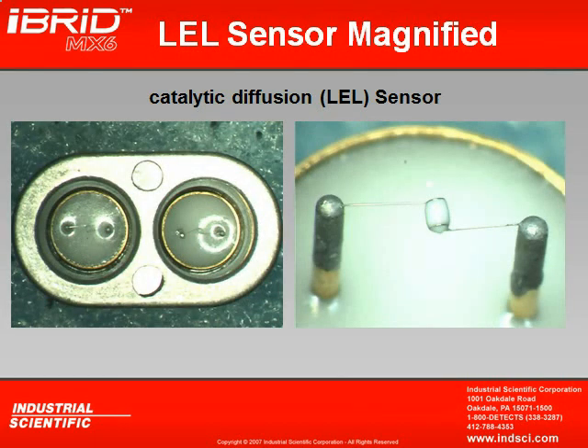So if we could actually see inside of a combustible sensor, this is what we'd see. Now we took these pictures underneath microscopes because, well, that's 1/1000th of an inch thin platinum wire. That's 7 times thinner than a human hair. Pictured on the left, you'll see I have circled, that's actually the sensing bead. Now the sensing bead is very porous, kind of like a piece of charcoal, and that is so that the combustible gas vapors will actually mix with the electrochemistry and cause a reaction. What you're seeing on the right, though, this is my temperature compensating bead. Now the temperature compensating bead, you'll notice, is very smooth.